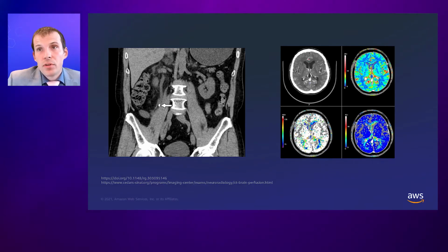The actual number of images that we present to radiologists will be different depending on the indication. So at the end of the day, we have literally hundreds of thousands of settings needed to be programmed across a medium-sized hospital CT scanner fleet to reflect the wide range of indications and patient sizes a hospital needs to image.